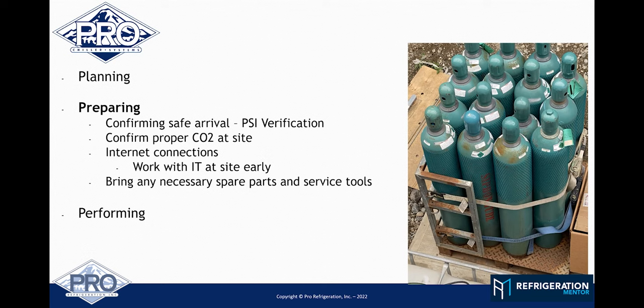Depending on where you're at, like I've heard lots of people say, just like you, 100 PSI, 9, 10 bar, whatever it is, get it to a point where you're above that triple point because you have dry ice. When we first did our first charging of our first system, I was charging through a high pressure or transcritical manifold set, and you're dealing with small fittings and switching bottles. Next thing I know, it seemed like it wasn't moving, and what I'd done was built up some dry ice inside my gauge set. I found that out, pulled the hose, gave it a little pressure, and the dry ice popped out.